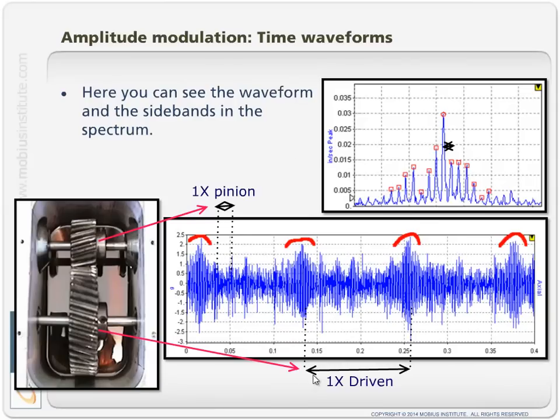In this case, and sorry, these arrows have gone a bit funny, little technical difficulties that chew up time, but anyway, we've got damage on this gearbox, some eccentricity on both of them, a little bent shaft in one case, eccentricity in the other case, just to simulate this fault. And so there's our modulation, there's the turning of the lower speed gear, the driven gear. So there's the modulation, modulation, as its teeth go harder in mesh, weaker in mesh, harder in mesh, weaker in mesh.